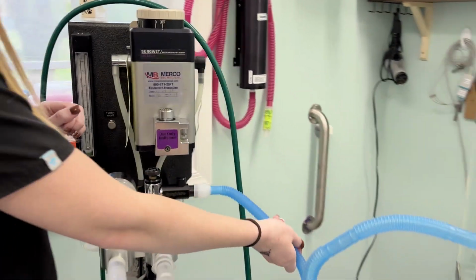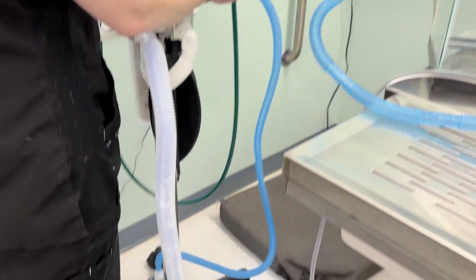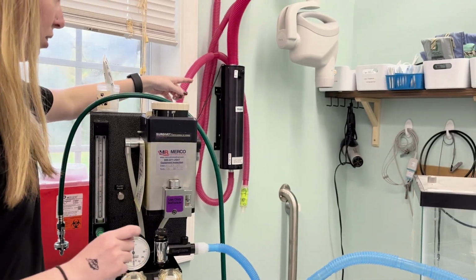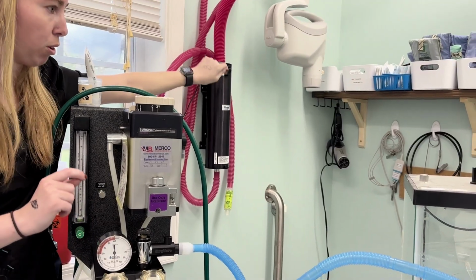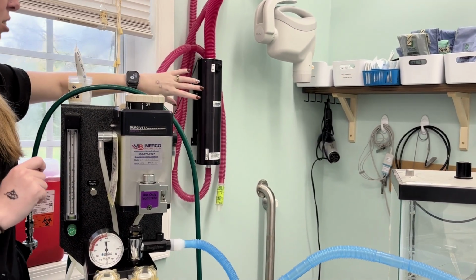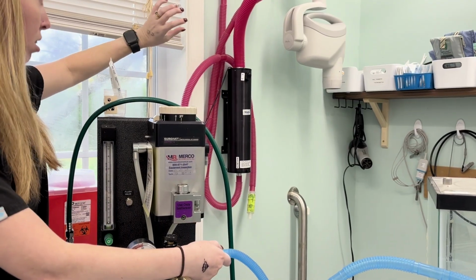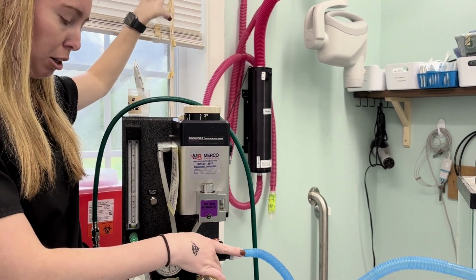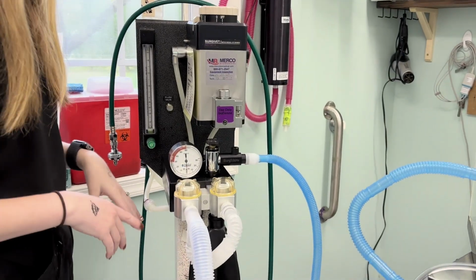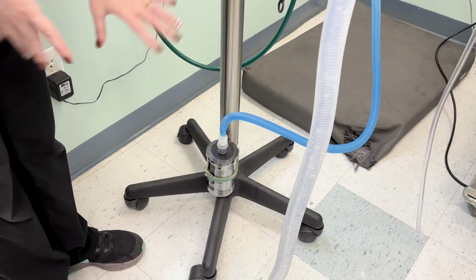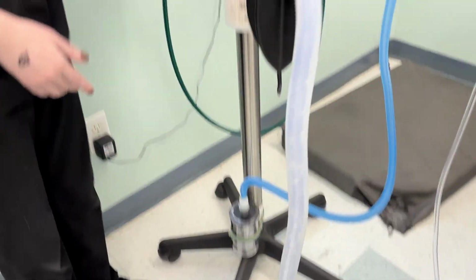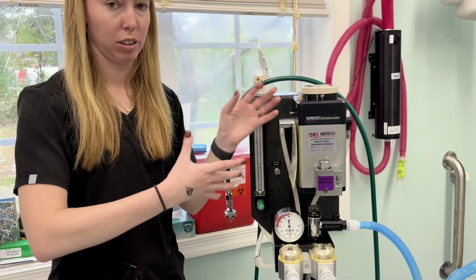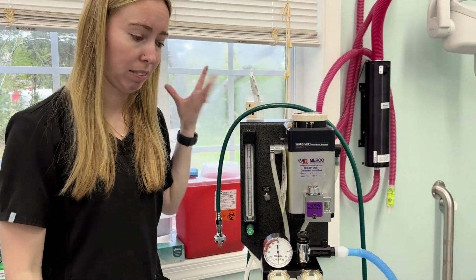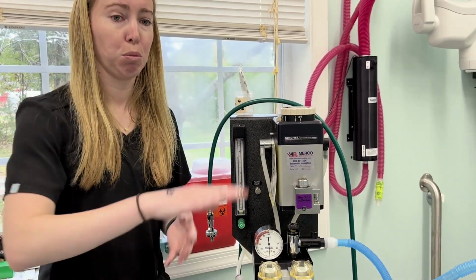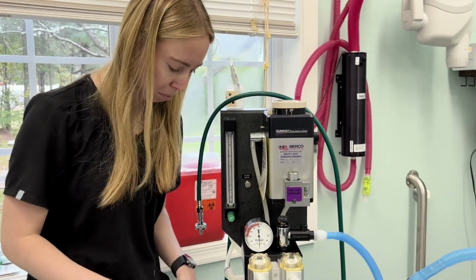Over here is where we connect this part to our scavenger. We do have an active scavenger on our wall, so we turn it on before every procedure, and it connects directly to this and goes outside the building. The other scavenger that we have is attached to the anesthetic machine. That's just a charcoal canister that we can connect to if we have to transport this machine anywhere and we're not next to the active scavenger, so we're able to move around anywhere we want in the hospital.